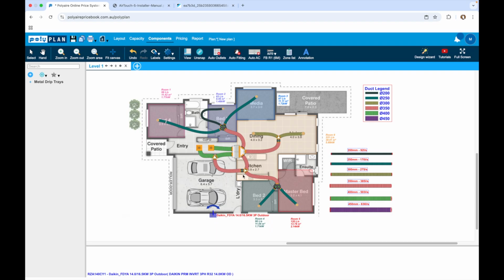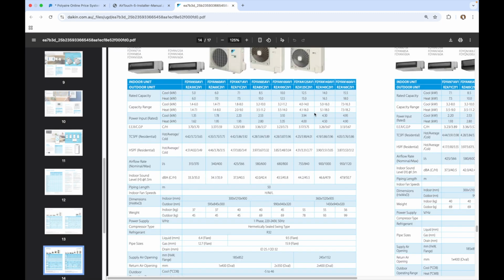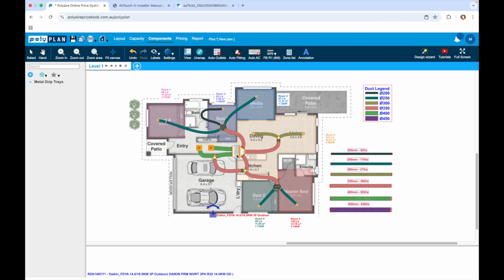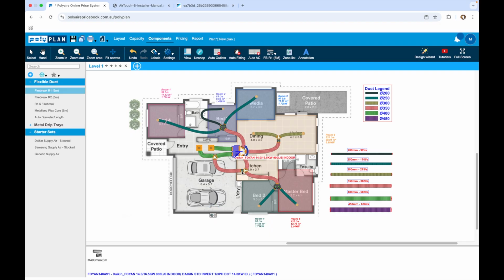And even if this opens up to a point and closes to a point, once this outdoor starts, it starts on its minimum speed, which if you look at a Daikin unit for 14 is about 5 kilowatts out of 14 that it can run at. So the thing will just start to open, it will just start to speed up at about 5 kilowatts while it's bleeding some cold air in here. And because at 5 kilowatts of running speed, it's already keeping its coil cold enough while it bleeds a little tiny bit of air, it just won't really ramp up any higher than that.